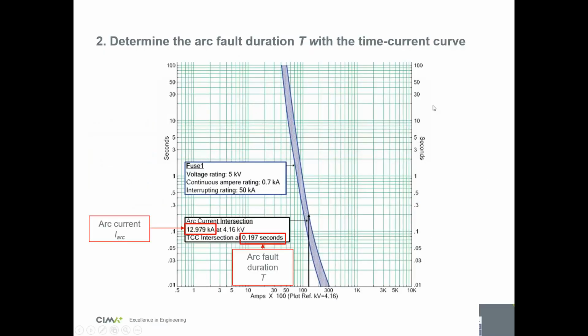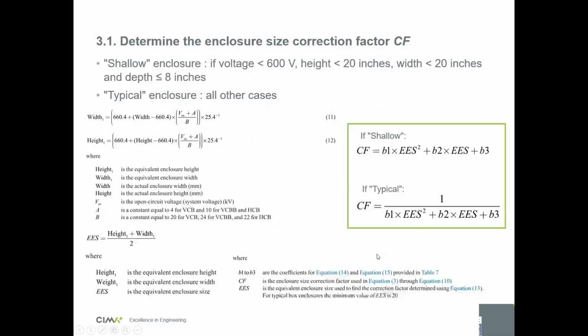So once you have your I arc, same thing, you go on the time current curve, you put your fault current on the x-axis, then you go up, you go to your total clearing time, and then you go sideways, and then you find your fault clearing time. So now, as I stated before, the new standard has enclosure size now in its equations.